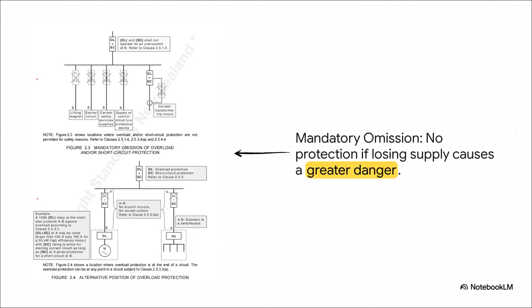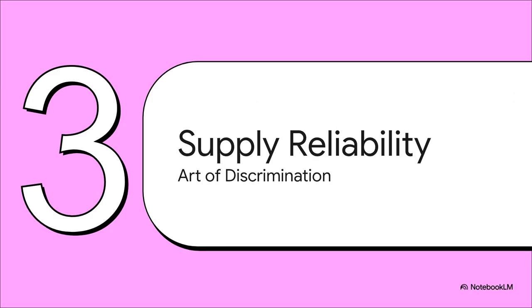Now, this might seem totally backwards at first, but it highlights a really deep safety idea. You have to weigh the risks. Think about a giant electromagnet on a crane lifting a ton of steel over people's heads. What's the bigger danger? The cable overheating or that magnet suddenly shutting off and dropping its load? Yeah, the standard is crystal clear here. In certain cases, where losing power is actually more dangerous than the overcurrent itself, you must leave out the overload protection.